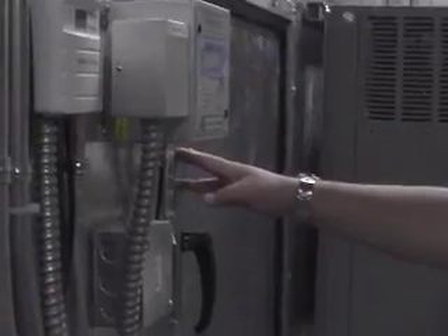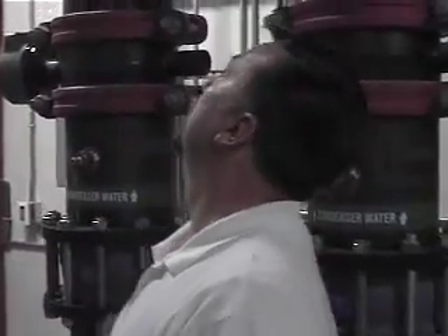Well, I guess we can go up to the penthouse and start walking through the equipment up there until we get to a point to break for lunch, and then we can pick up where we leave off and go till we run out of stuff to talk about. Where the damper is and the inlet of the fan, and then your output side of the air fan is in here. Coil in there. Yeah. So if you look, the coil is on one more section down.